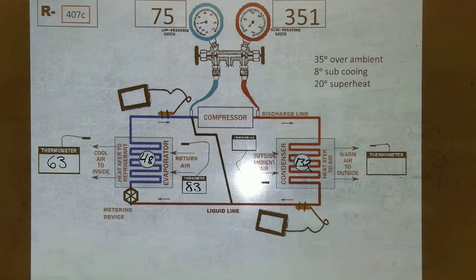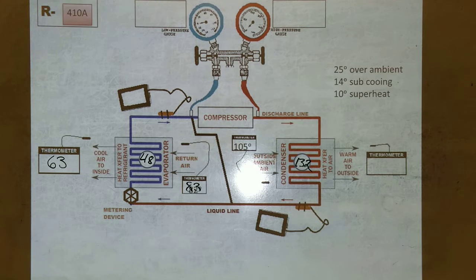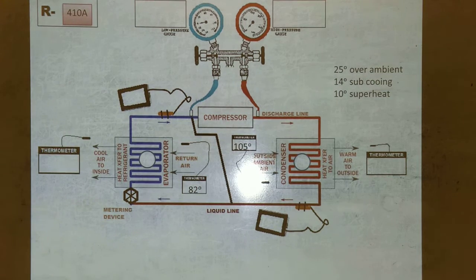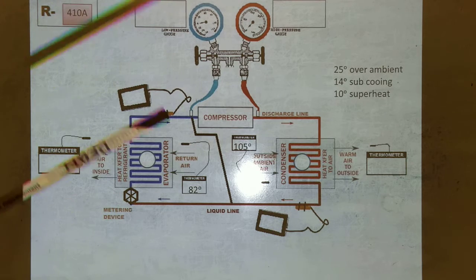If you're gonna go check a unit out, let's check it out before we get our subcooling and superheat on this one. Don't tell me the wrong one. We'll go back to that. You're gonna check the unit out. It could be working fine. You're out there looking at it to make sure it's okay because you're doing maintenance. It could be a bunch of commercial units all lined up on the roof, let's say.